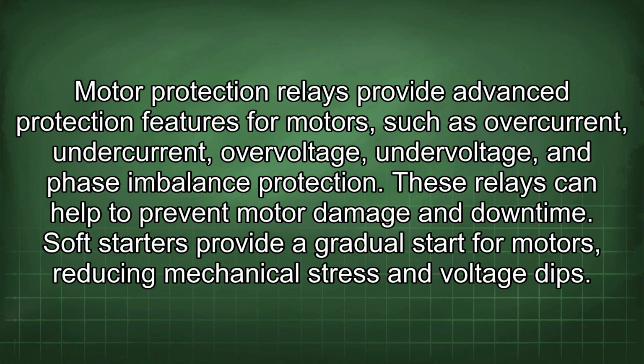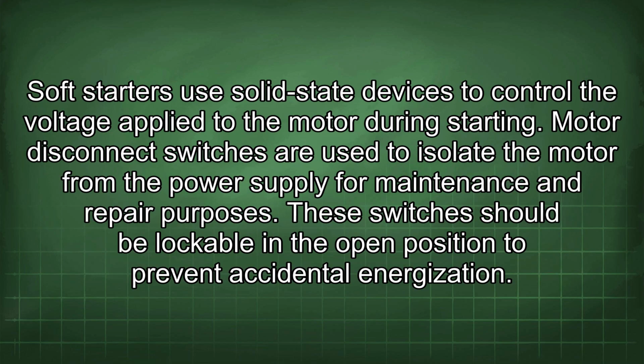Motor protection relays provide advanced protection features for motors, such as overcurrent, undercurrent, overvoltage, undervoltage, and phase imbalance protection. These relays can help to prevent motor damage and downtime. Soft starters provide a gradual start for motors, reducing mechanical stress and voltage dips. Soft starters use solid-state devices to control the voltage applied to the motor during starting. Motor disconnect switches are used to isolate the motor from the power supply for maintenance and repair purposes. These switches should be lockable in the open position to prevent accidental energization.